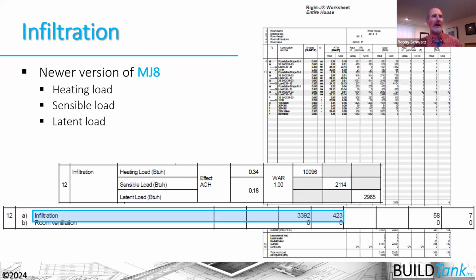So we now have Manual J8, which is a newer version of the Manual J software. And we can see that the infiltration load here is defined a little bit better. So you probably also want to ensure that your contractors are using the most recent version of the Manual J software to be able to get a better calculation here.